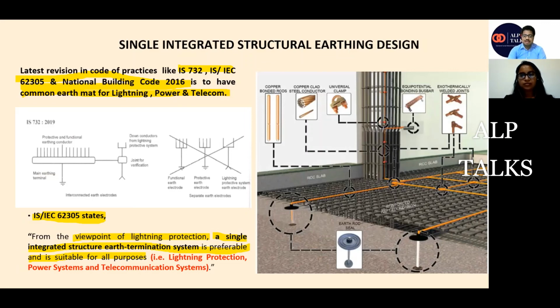Generally telecom and lightning protection are more sensitive compared to normal systems. Lightning current travels with a waveform of 10 by 350 microseconds, while we design our electrical and electronics systems for 1 second or 3 seconds, which is much more severe than 10 by 350 microseconds. So when I design a complete grid considering a 1 second fault current duration, and calculate the ground potential rise, step potential, and touch potential for the grid, at that time I can connect the lightning protection system also with the same grid.